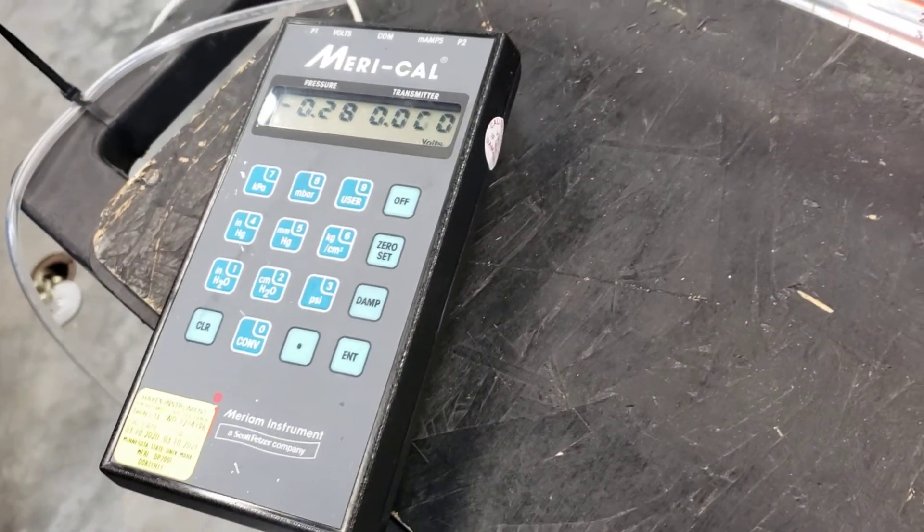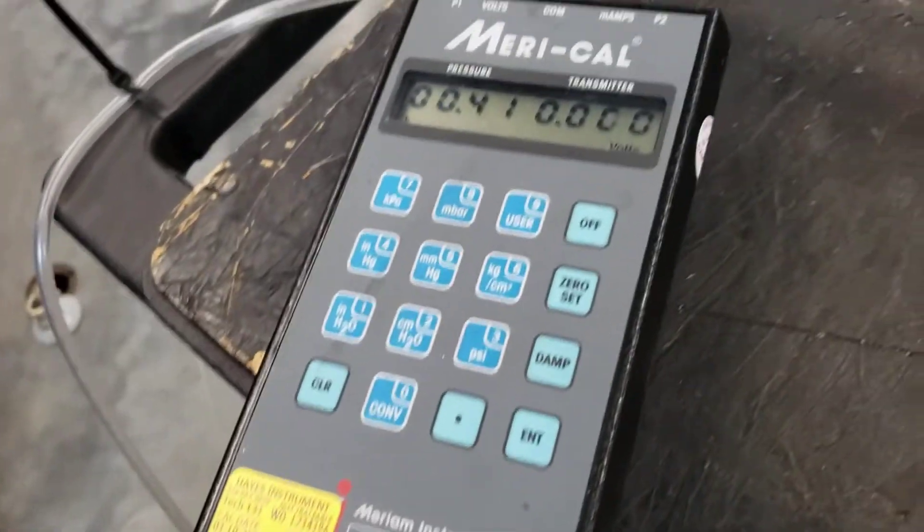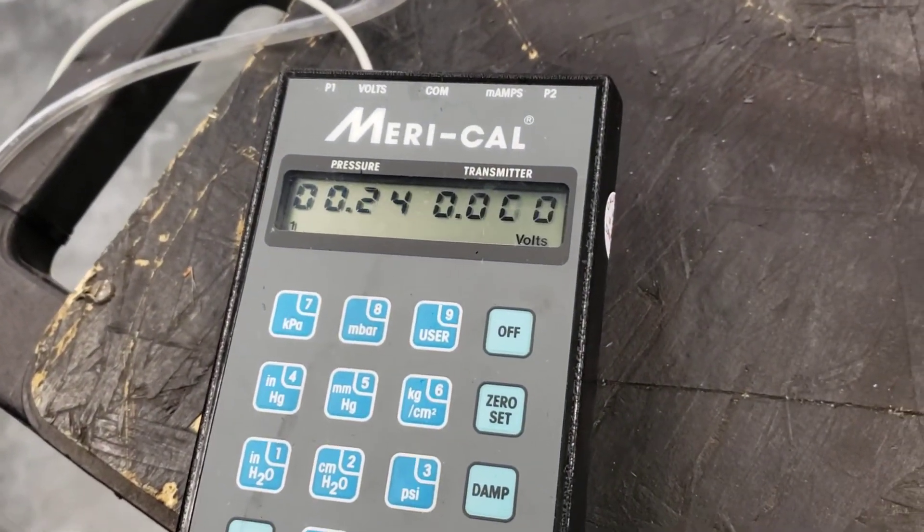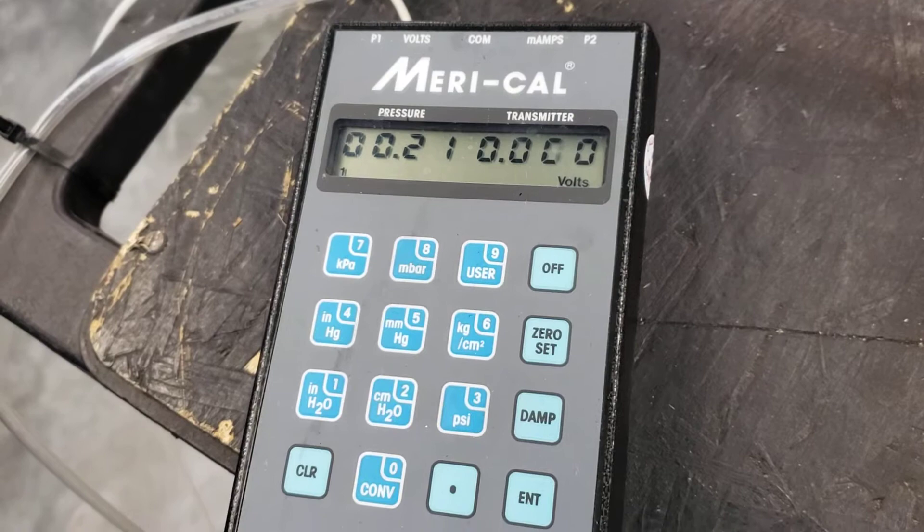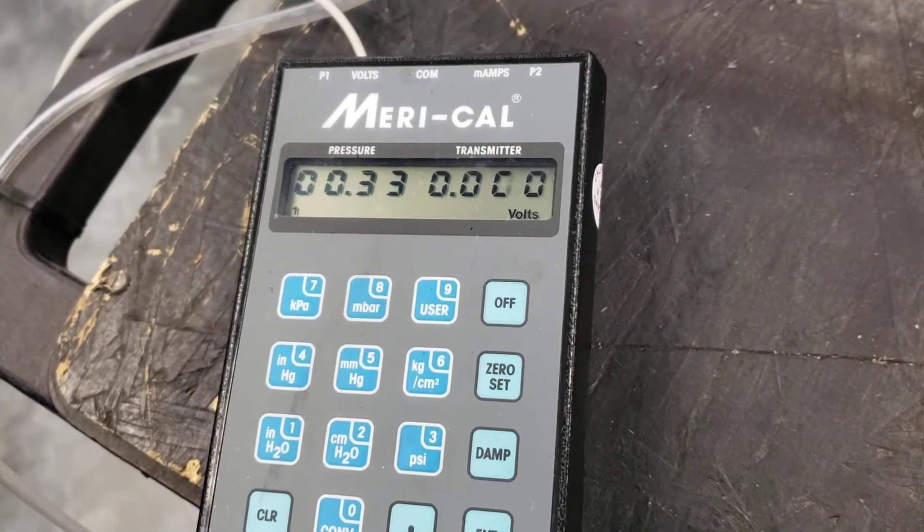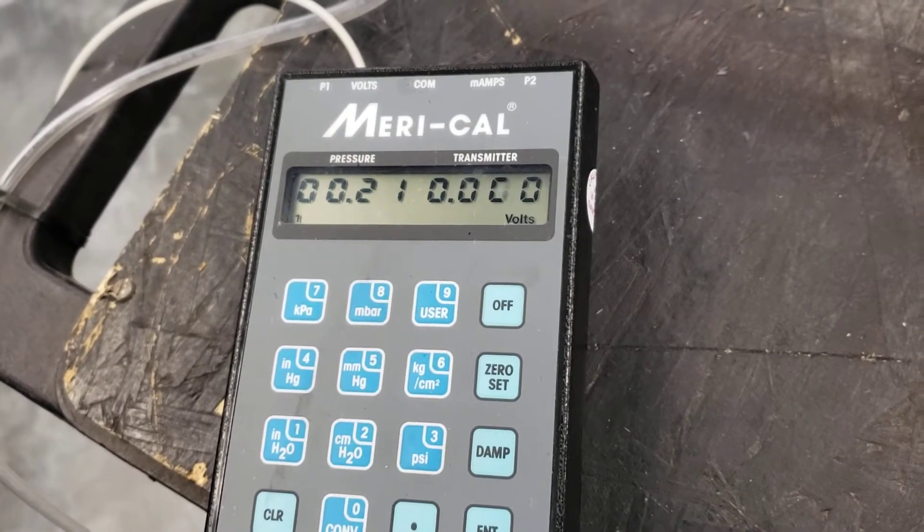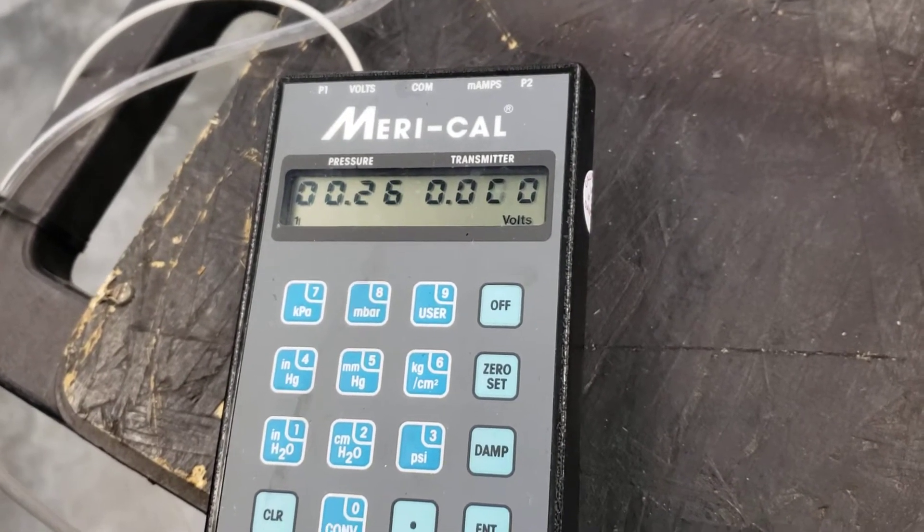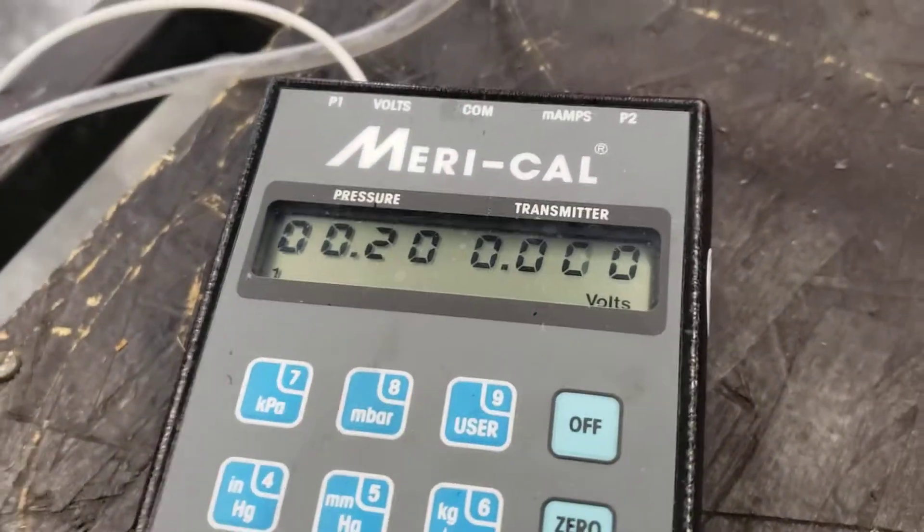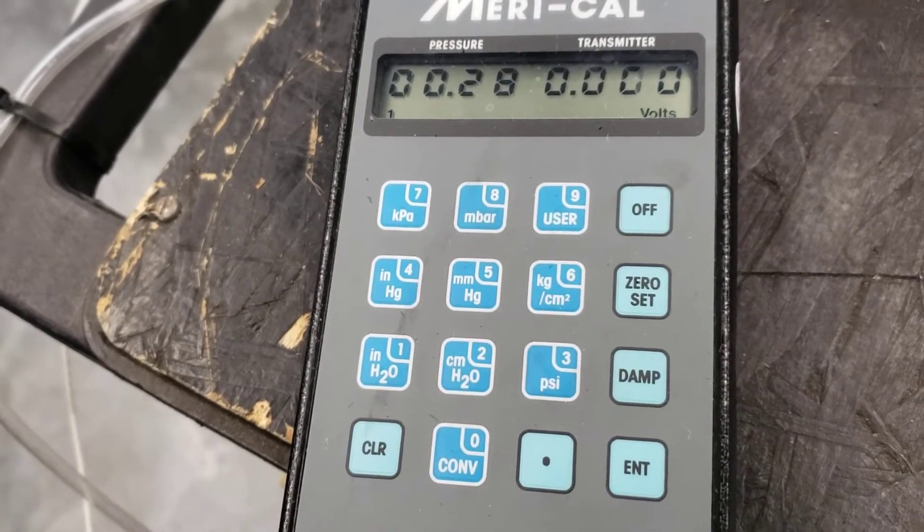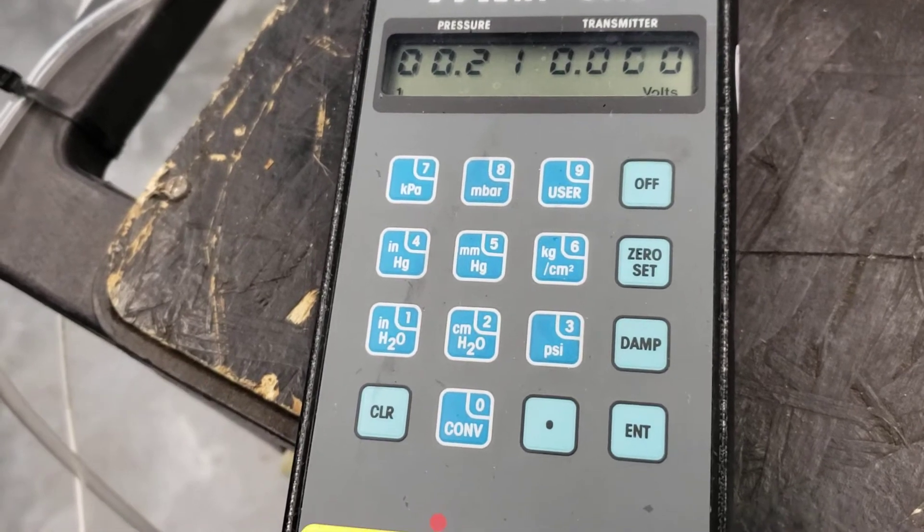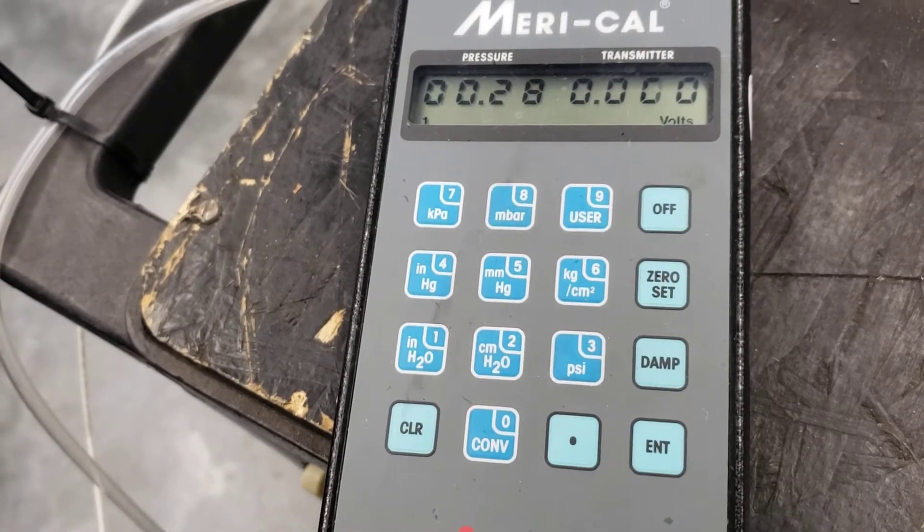Now we're going to change that manometer line to the digital one and you will see that it will respond very quickly. It responds very quickly but it is not very smooth. It's kind of flicking all over. It's just the way that it responds. It will eventually get about 0.31, which we got from the manual manometer.